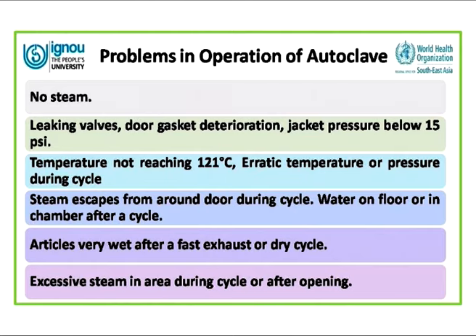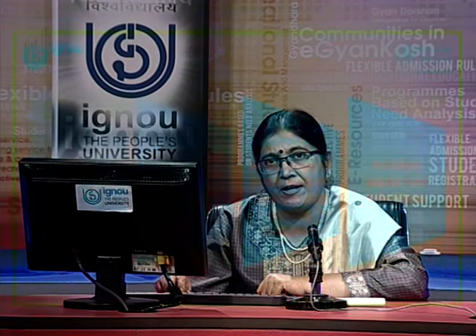For example, there is no steam, there may be leaking valves or the door gasket may deteriorate, the temperature may not reach at the right time and the steam may escape around the door during the cycle. There may be water on the floor or in the chamber which should not be there, and you may get the articles very wet. Excessive steam in the area during the cycle or after opening can also be encountered. So if you have been operating an autoclave you may have come across some of these problems. But still the autoclave has a number of advantages.